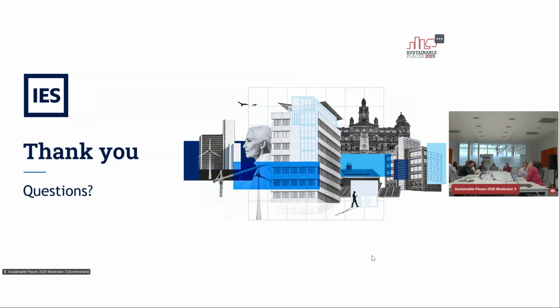And actually, there are levels of detail for digital twin. So you can create a digital twin when you have only 1 meter data, so 1 temperature sensor. So you can already start creating a digital twin. I take an example of a manufacturing process inside a big warehouse. They replaced the machinery, so they changed entirely their process, and there was mechanical, chemical and electrical heat release. So they couldn't just put a meter to measure it. So they had, just for 2 weeks, temperature sensors and weather data on the rooftop.